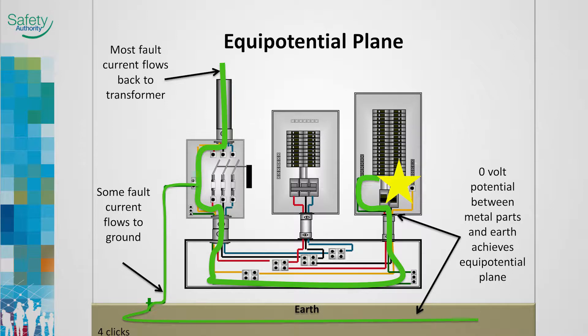A shock hazard is created when there is a voltage potential between two points. When equipment fails and a fault occurs, the metal parts of the equipment carry the fault back to the power supply neutral. As this fault current flows, there is a voltage rise across the metal electrical equipment. Good effective bonding provides a low impedance path which results in a low voltage rise, reduced risk of electrical shock, and faster operation of the fuse or circuit breaker and less equipment damage.